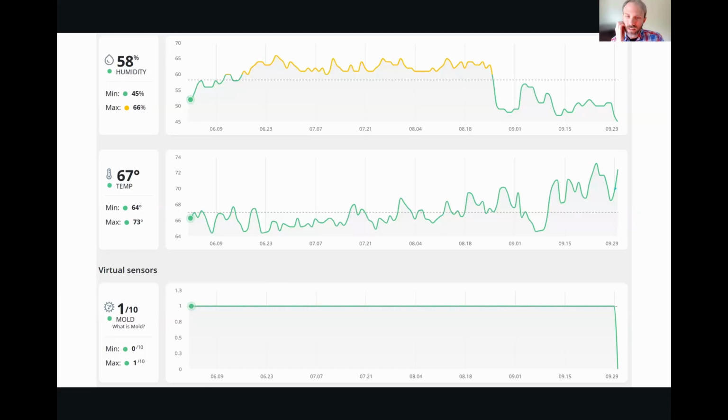So I went down and looked, and yeah, the breaker was out, but also there was an issue with the dehumidifier, and we needed to have an HVAC come in and do a quick service. So once we did that, you saw a quick drop in the humidity and it stays low. And so, it worked. But you can also see these dehumidifiers put out a lot of heat. And so, it put a lot of heat into the basement and raised the temperature as well.